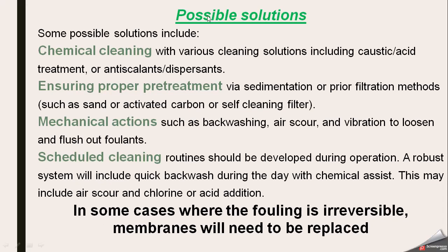So what are the possible solutions? Some generalized possible solutions include chemical cleaning. We will clean the membrane with a suitable chemical like caustic, acid treatment, anti-scalant or dispersant, depending upon the type of fouling. And very important, ensuring proper pre-treatment, via sedimentation or prior filtration methods such as sand, activated carbon or self-cleaning filter.